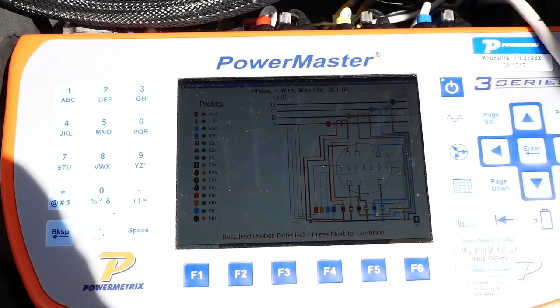It's showing us our primary connections. It always shows you the color diagram before the meter test and then before the CT test, because now you have primary connections. You have to connect on the primary side to be able to test those CTs, because you're comparing the primary versus secondary current. So it's saying, okay, it looks good on the primary connections down here at the bottom of the screen - PIA, PIB, and PIC. Those are my primary connections. It's telling me I need to be on all three phases for this 9S 120/208 3-phase 4-wire system.